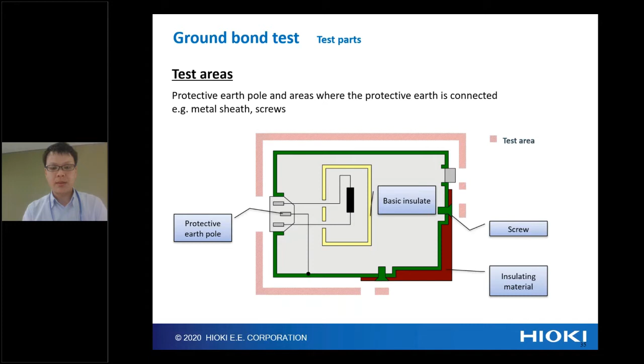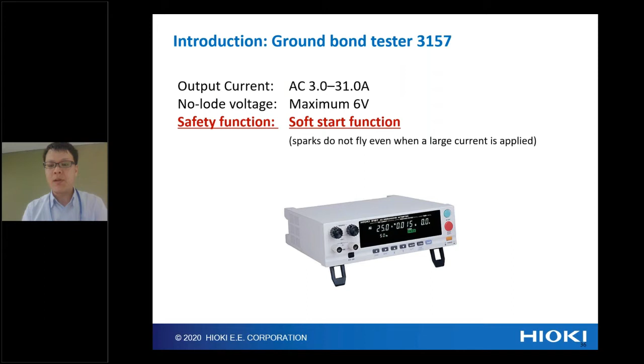Okay, so we have a 3157. This is our ground bond test. Output current: this instrument can apply AC from 3 to 31 ampere. And of course, no load voltage, maximum 6 volt. We also have a special feature, the soft start function. Sparks do not fly, even when a large current is applied.